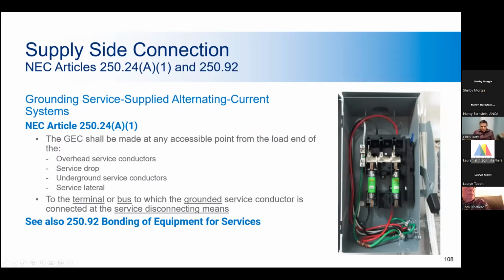Here we see a supply side disconnect that does have a proper neutral to ground bond. You can see the white conductor and the green conductor are bonded through this green bonding screw. And that's done correctly for the AC supply side connection, as you can see right here.